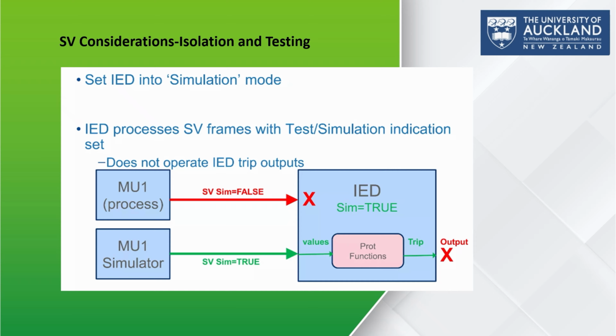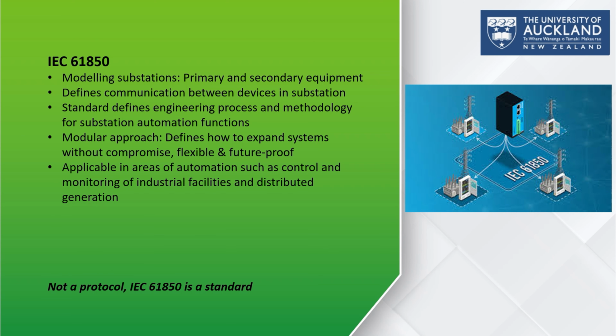So IEC 61850 is an international standard designed to simplify, unify, and improve communication within electrical substations. It provides a common framework that allows devices from different manufacturers to communicate seamlessly, ensuring interoperability and reducing engineering complexities. The standard supports detailed modeling of substations, covering both primary equipment such as transformers, circuit breakers, and disconnectors, and the secondary equipment including protection relays, control units, and communication devices. By representing all the components in a structured, object-oriented format, IEC 61850 enables consistent data exchange and efficient system integration.